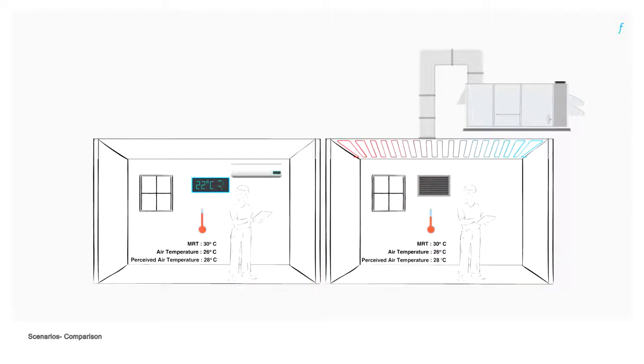A room with a regular air-based cooling system has a higher mean radiant temperature and therefore needs a low room air temperature to make the occupants feel comfortable. A radiant cooled room, however, has a lower mean radiant temperature and can provide the same cooling effect at a relatively higher room air temperature. In radiant cooling systems which have a dedicated outdoor air system as well, the air requirement is considerably lesser than a regular air conditioner which is also reflected in the reduced power consumption of the overall system.